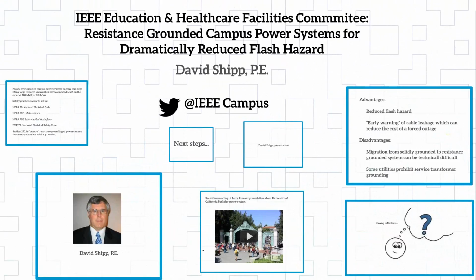Yeah. Well, I did want to make a statement about the money flow. And this gets into the cultural issue, as you know, that our industry is very much a compliance industry. I'll get back to the innovation, all the bloviating and the posturing and the pretensions of innovation. They're really not serious about it. They're just serious about saying so. So the example I like to use is that they would rather hire 5 compliance folks for $100,000 each to go around checking incident energy labels and conformity to the code for the incident energy that exists there, rather than spend the same $500,000 to reduce the flash hazard to begin with.